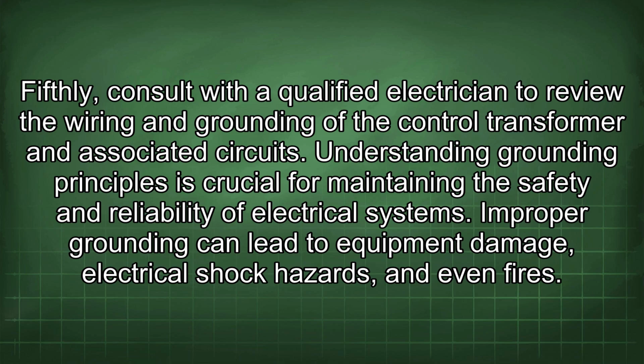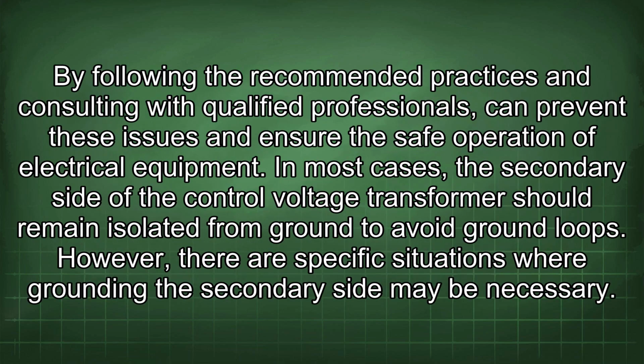Understanding grounding principles is crucial for maintaining the safety and reliability of electrical systems. Improper grounding can lead to equipment damage, electrical shock hazards, and even fires. By following the recommended practices and consulting with qualified professionals, you can prevent these issues and ensure the safe operation of electrical equipment. In most cases, the secondary side of the control voltage transformer should remain isolated from ground to avoid ground loops. However, there are specific situations where grounding the secondary side may be necessary.